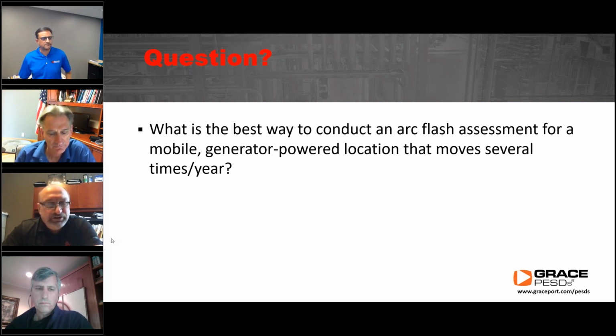So if you did do an incident energy analysis study for a fixed generator, the issue would be cable lengths, just thinking out loud, to any sub-distribution off that generator. But if it's multiple generators, right, that's another topic as well. Ultimately, we have to recognize there are two methods to determine additional protective measures when you do an arc flash risk assessment, and the arc flash PPE category table method could be used as well.